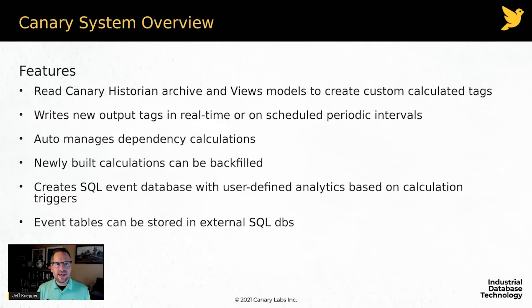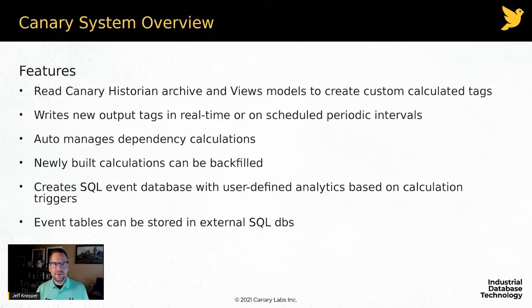Your calcs can have dependencies, so you can create multiple tiers of calculations that build off of each other. Once you've created a first calculated tag, it might live in another calculation as part of a second calculated tag. We automatically manage those dependencies — if something happens upstream, your downstream calculations are aware of that. This includes a really neat feature: the backfilling of calculations.